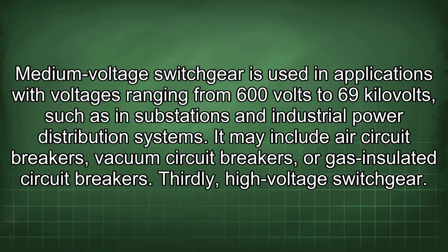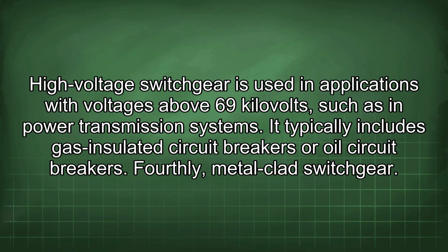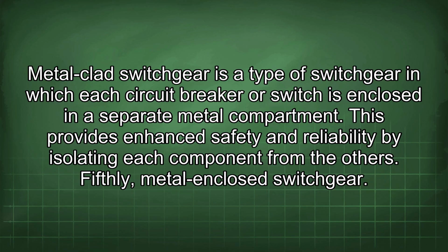Thirdly, high-voltage switchgear. High-voltage switchgear is used in applications with voltages above 69 kilovolts, such as in power transmission systems. It typically includes gas-insulated circuit breakers or oil circuit breakers. Fourthly, metal-clad switchgear. Metal-clad switchgear is a type of switchgear in which each circuit breaker or switch is enclosed in a separate metal compartment. This provides enhanced safety and reliability by isolating each component from the others.